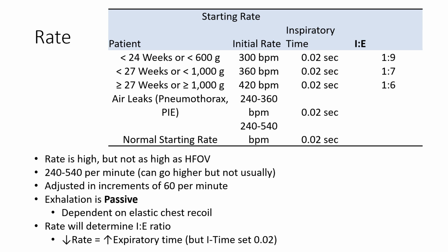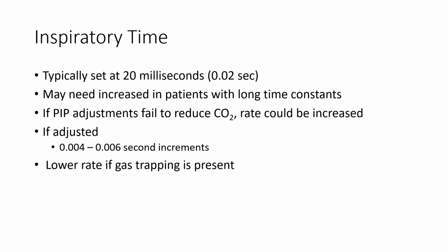Patients can spontaneously breathe during jet ventilation as the conventional ventilator is also supplying a constant flow of gas. The rate on the jet ventilator is similar to conventional ventilation in terms of management. Increasing the rate will increase the amount of carbon dioxide eliminated so long as it does not cause air trapping. Decreasing the rate will extend the exhalation time, which may improve gas exchange if air trapping is present. The inspiratory time should remain constant at 20 milliseconds.